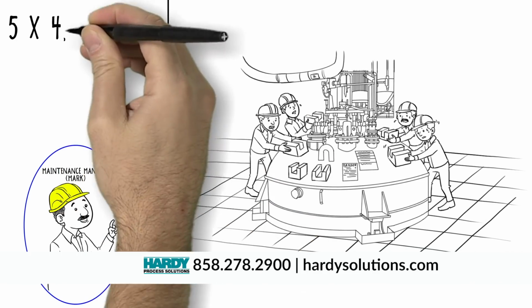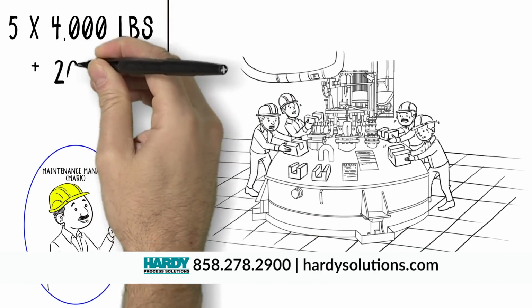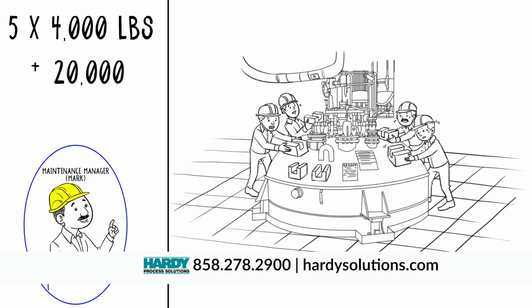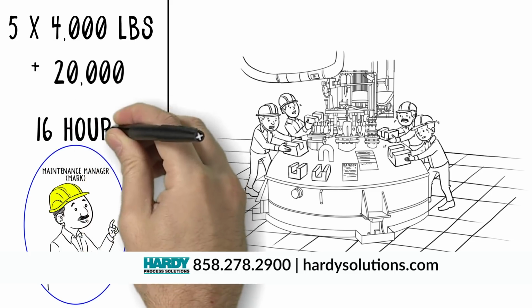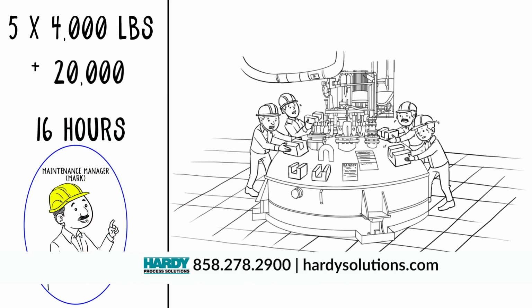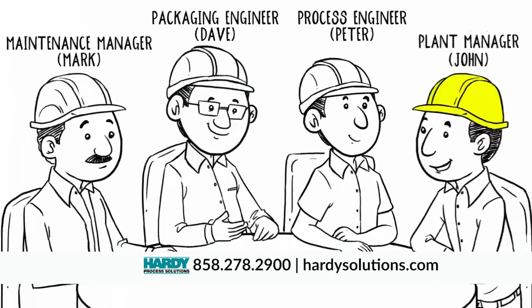There were 5 4,000-pound scales and 1 20,000-pound scale in each system. It takes us 16 hours to load test weights, calibrate, and validate all 5 scales. We have to load and unload the test weights, which takes time and raises safety concerns. It can't be rushed.